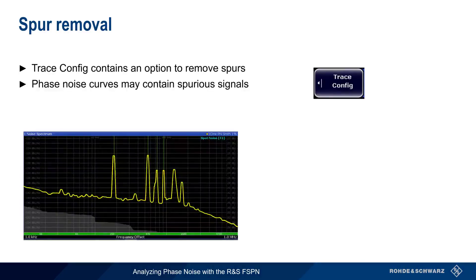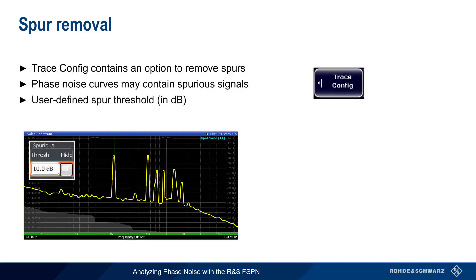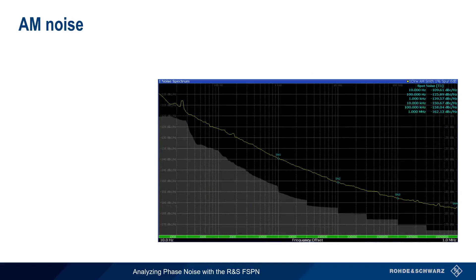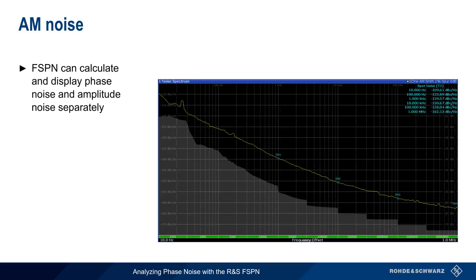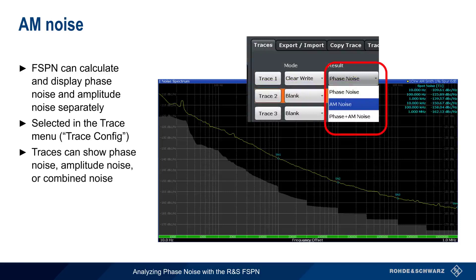Another display feature is spur removal, which is also enabled under Trace Config. Many phase noise curves contain spurious signals, which appear as peaks or spikes on the trace. Spurious signals or spurs are caused by interfering signals, not by phase noise, so we often want to remove them from our results. This is done by defining a threshold in dB. Enabling spur removal hides spurs which lie more than this number of dB above the trace. One last trace feature to be aware of is the ability to choose which type of noise to plot. The FSPN can separate phase noise and amplitude noise, and display the combined result, or plot them separately. In the Trace Config menu, we simply select whether we want phase noise, amplitude noise, or both.